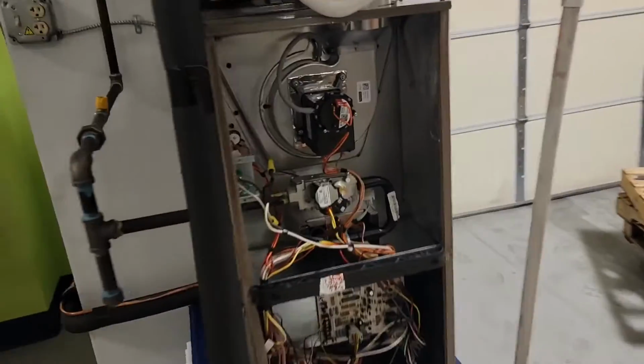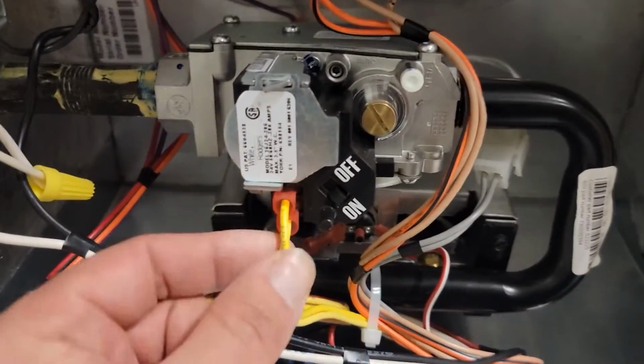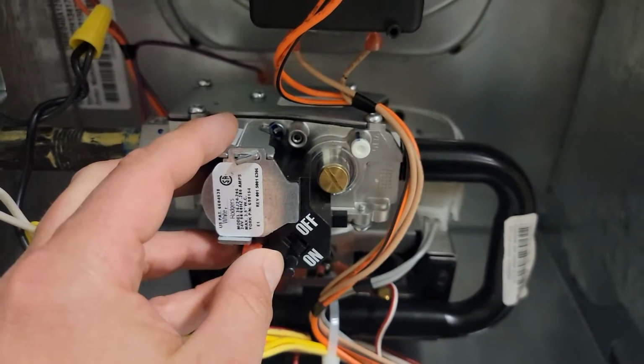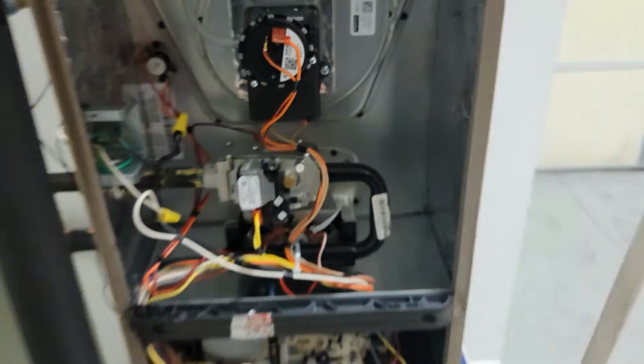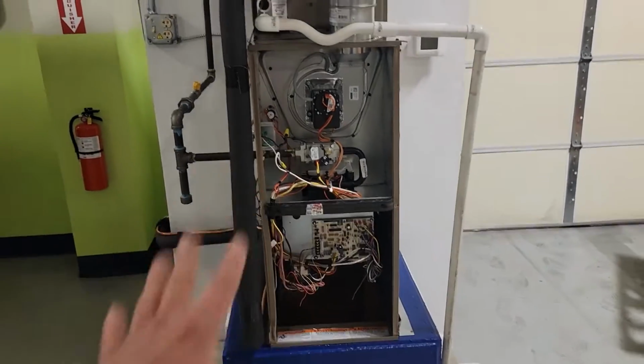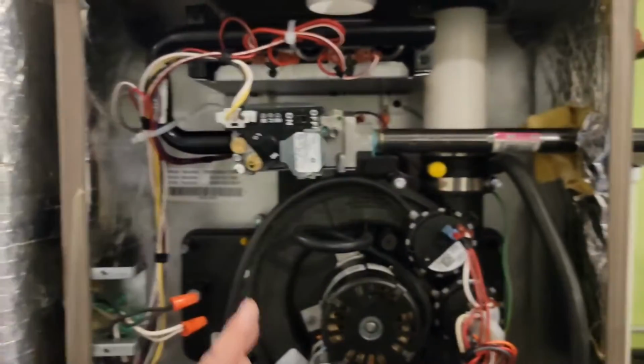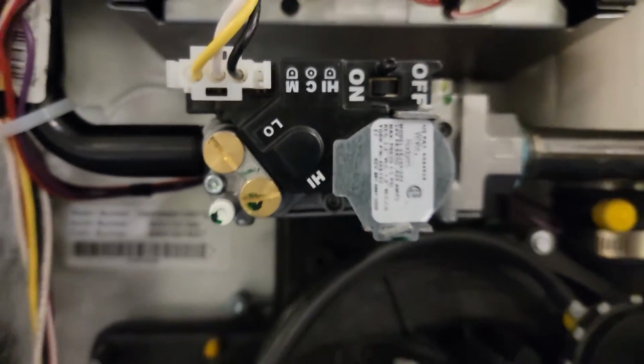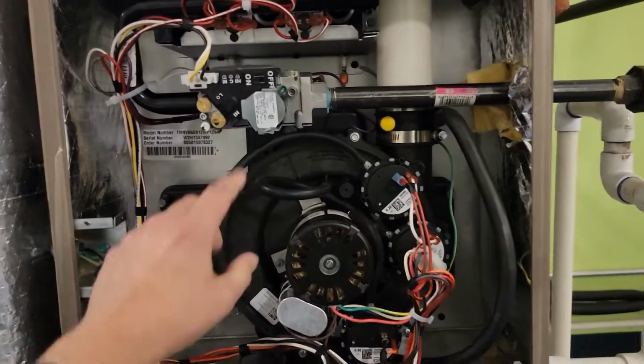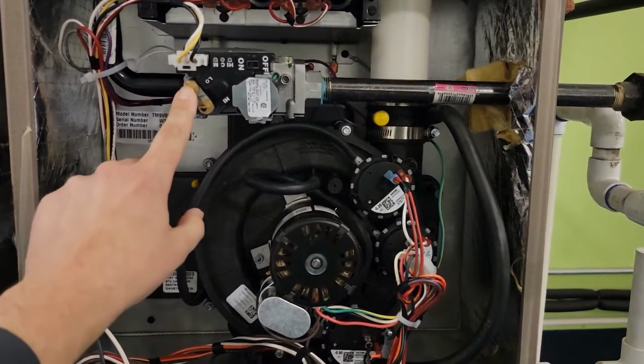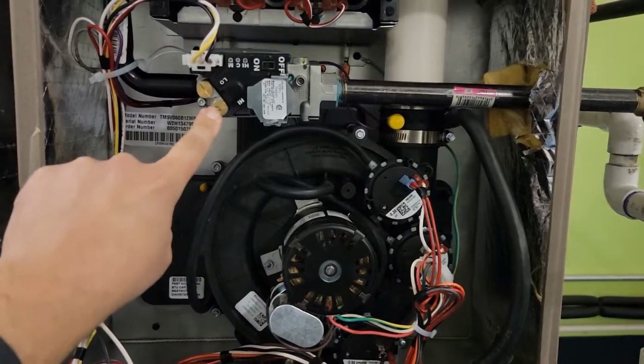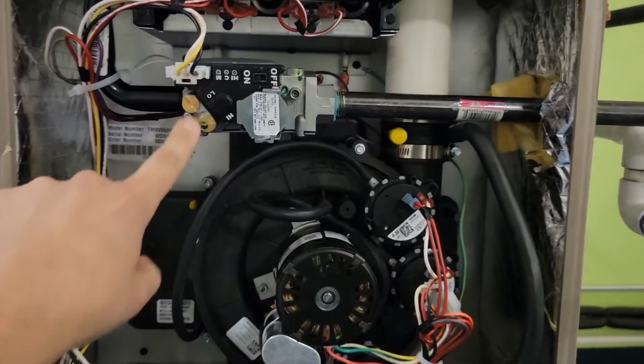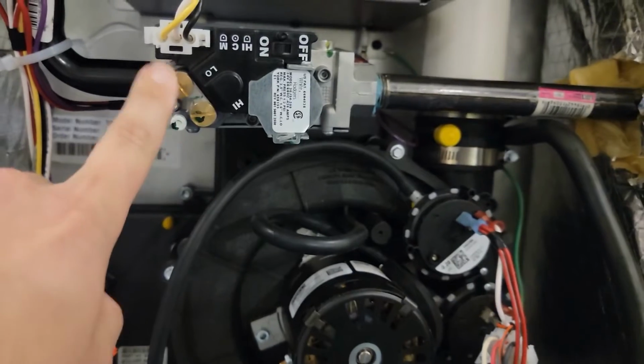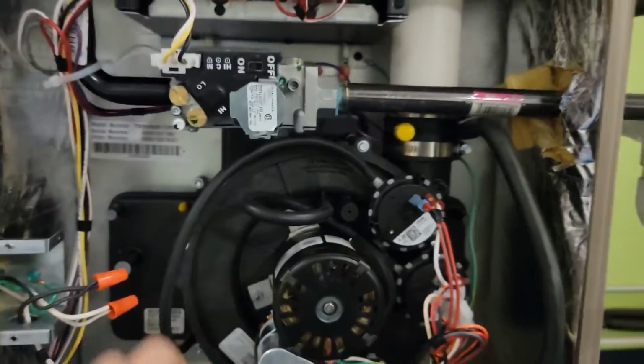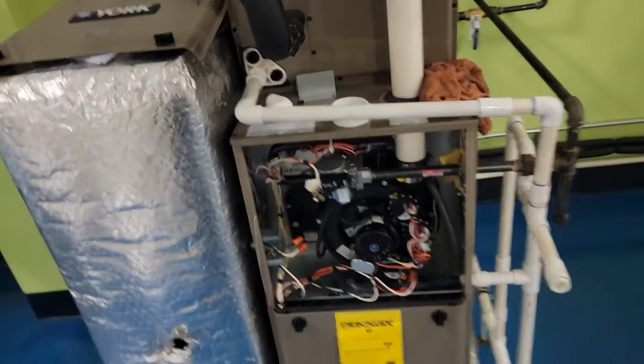So first, let's look at the 80%. This is a single stage gas valve. Two wires come into it, 24 volts, and they open and close this valve, and it only burns at one pressure, and that's 100%, okay? Because single stage burns at 100%. This right here is a 90% furnace with a two-stage gas valve, and you can see there's a low and a high stage. And if you are propane, of course, that low stage would be probably 6.7 or 7 inches of water column, and the high stage would be 10. And then of course for natural gas, it would be around 1.7 to almost 2 inches of water column for the low stage, and then high stage would be 3.5 inches of water column.